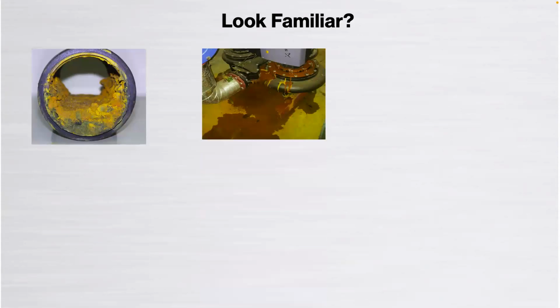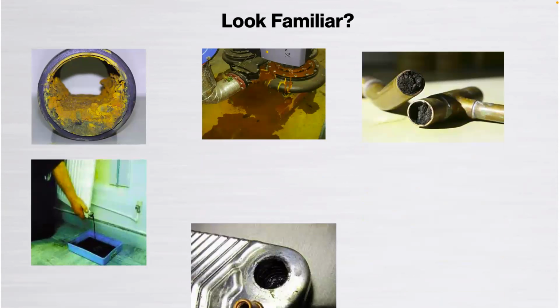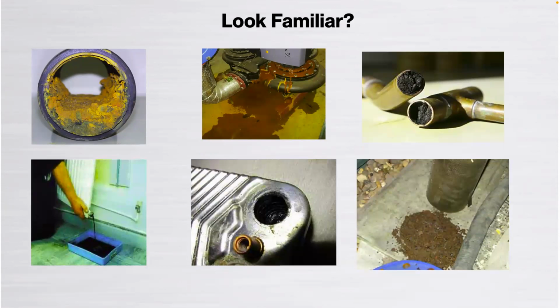So what does it look like? I'm just going to throw some photographs up here. This is kind of what it looks like. Starting top left, what we can see here is the deposit of suspended solids and settleable solids. This is really where flow rates have reduced, so we're not meeting the ASHRAE minimum flow rate requirements through a set diameter size of pipework, so we're allowing these fine particles to settle out, and that's what they can look like after a period of time. And of course, then we're impacting the volume of water and the flow rate that we can put through that piece of pipe, affecting our delta T.